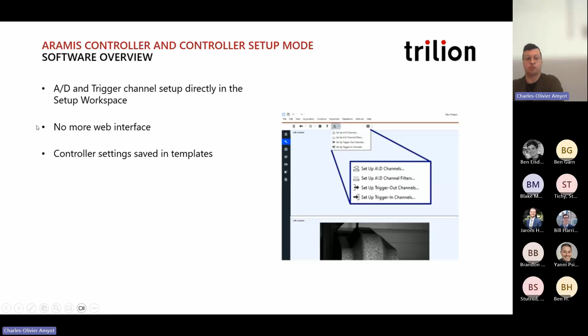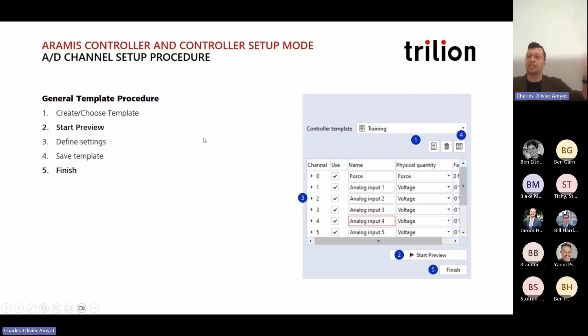There's no more web interface required, and you can save all your settings as templates. For example, if you're always using your machine with a 10 kilonewton cell, you can create a controller template for 10 kilonewtons, setting analog signal 0 as force with whatever factor, analog 1 as your crosshead, and so on. Building these templates means you don't have to edit or save them inside individual project templates, but within your controller templates instead.